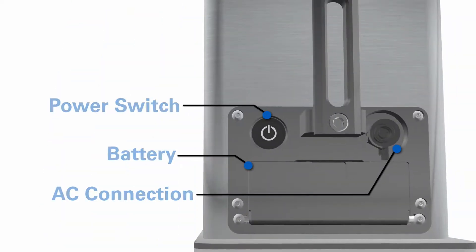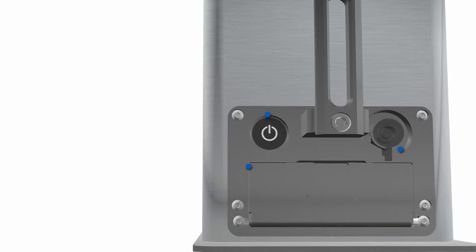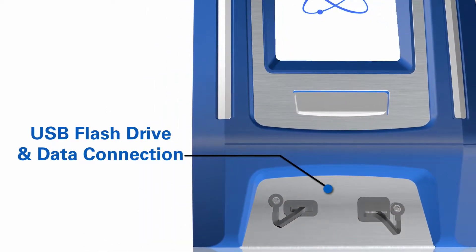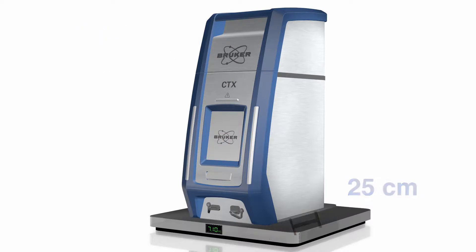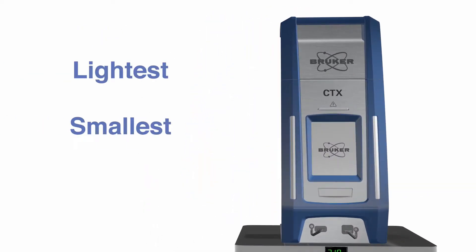The battery, AC connection and power switch are located at the back of the unit, while the USB connection for flash drive or data connection is conveniently located at the front. At less than 7.1 kilograms in weight and 25 centimeters in height, the new CTX is the lightest and smallest double safety interlocked portable XRF available.